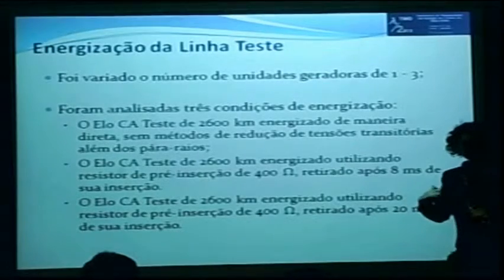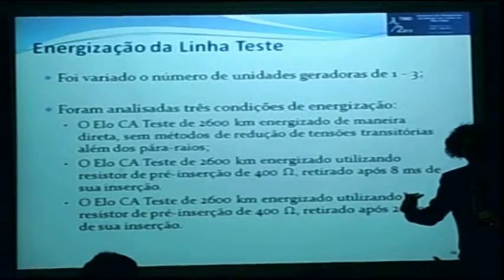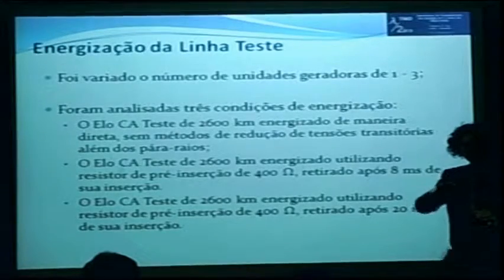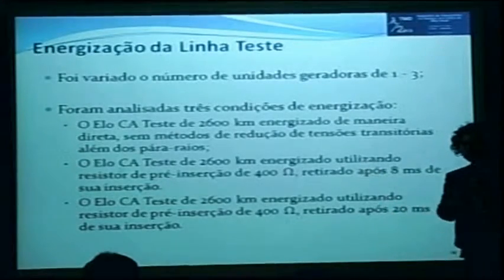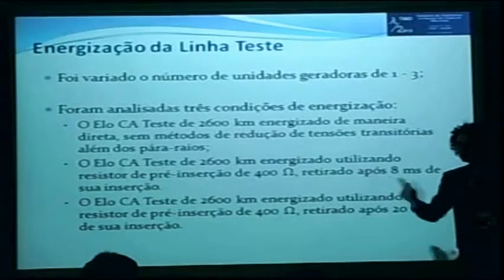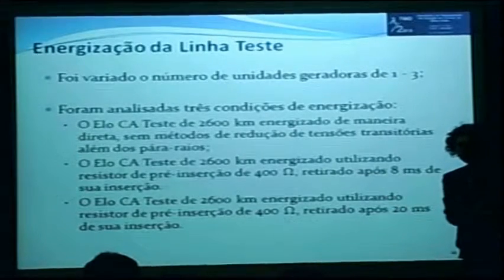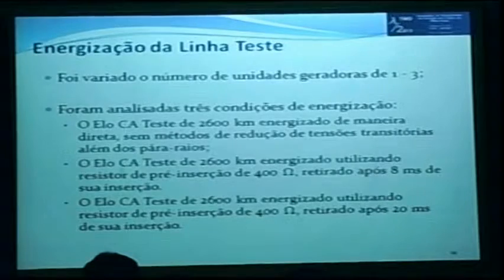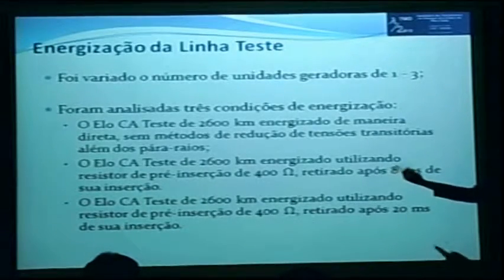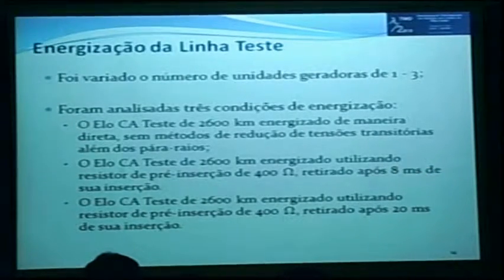8 milliseconds because this is the normal procedure, the normal maintenance time for this pre-insertion circuit breaker. 8 milliseconds would be enough time for a 400 kilometer, 300 kilometer line. For half wavelength, 1 transit time in our case corresponds to 8 milliseconds for the signal to reach the end of the line. So 16 milliseconds since the first disturbance came to the beginning of the line. I need at least more than that to remove the pre-insertion circuit breaker and have some efficacy.